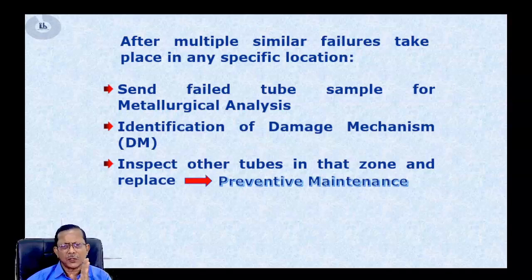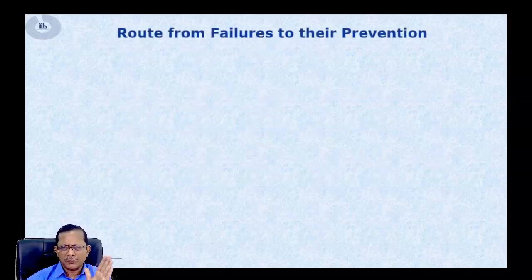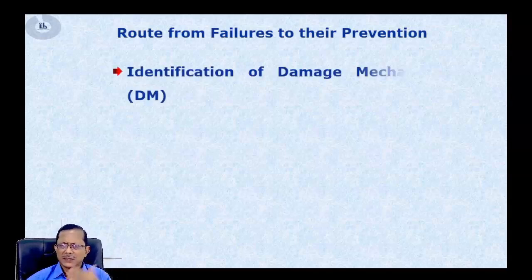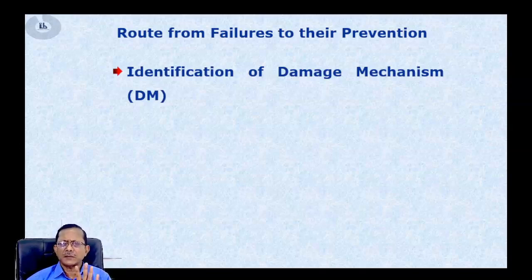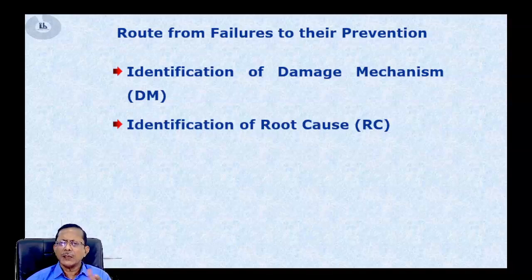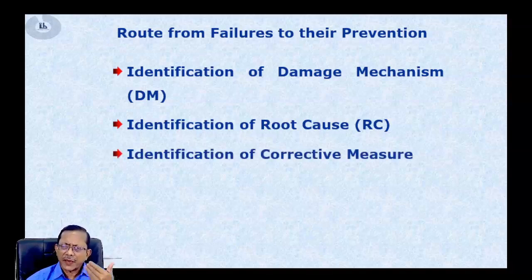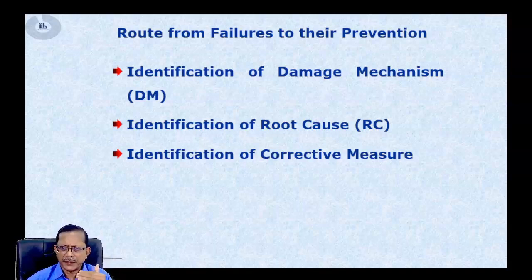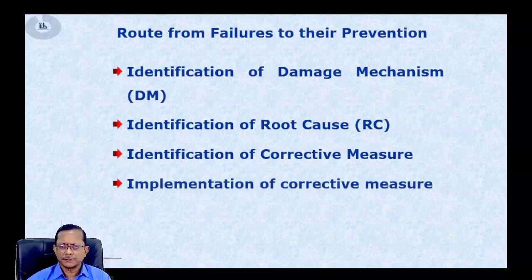What should actually be done — from failure to prevention — is: first, identify the damage mechanism. Once the damage mechanism is defined, find out what is causing it. That is the root cause. Once the root cause is found, identify what corrective actions should be taken to remove it, and then properly implement those corrective actions.